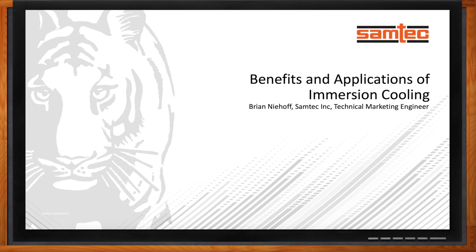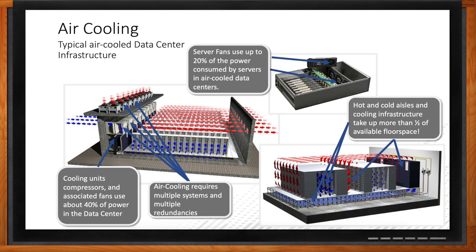Looking at the blade in the top right corner, you can see there are fans inside the box — their main purpose is to blow cold air across the components and keep everything within an operating temperature. However, those server fans actually consume about 20 percent of the power in a data center. And if you look at the picture on the left-hand side, the arrows are pointing to the HVAC systems on the roof, which consume about 40 percent of the power in a data center. Right there you're looking at a significant amount of power taken up without any compute function at all.